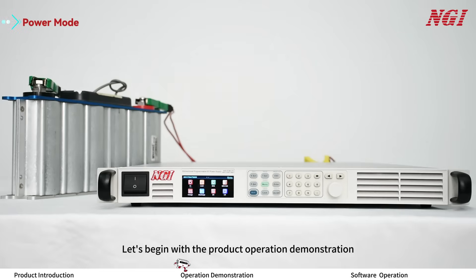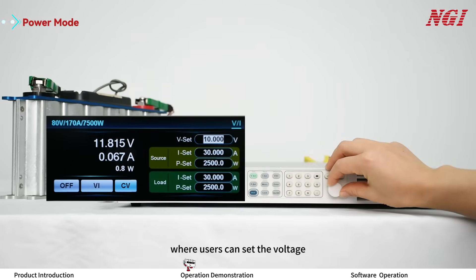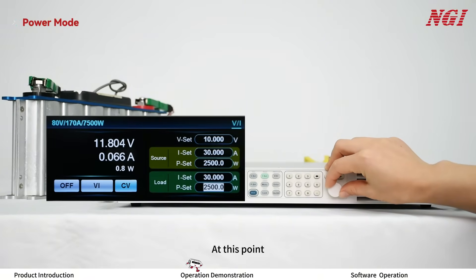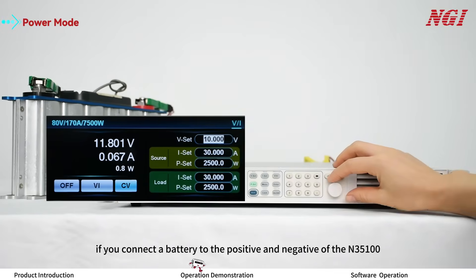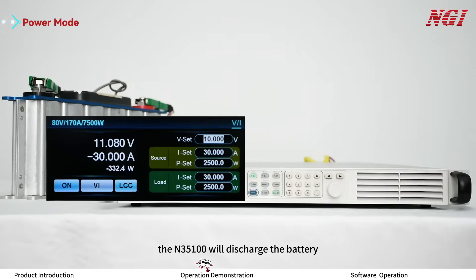Let's begin with the product operation demonstration. Upon powering on, the N35100 defaults to the power mode interface, where users can set the voltage source, current source, power load current, and load power. If you connect a battery to the positive and negative terminals of the N35100, it will perform the following actions based on the initial voltage of the battery: if the initial voltage of the battery is higher than 10V, the ON35100 will discharge the battery.